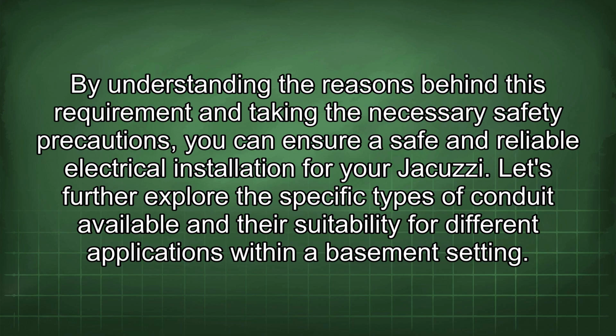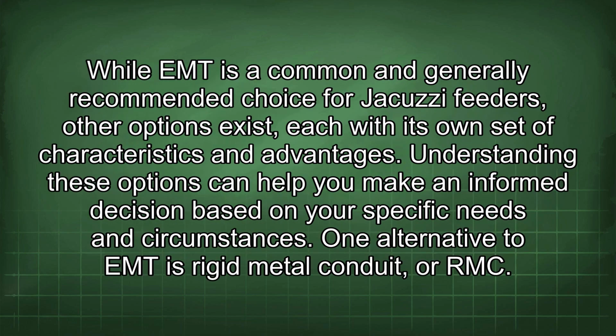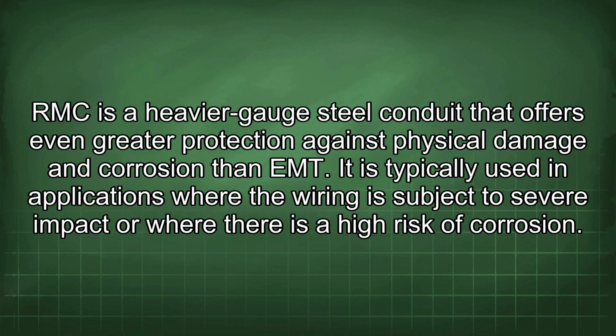Let's further explore the specific types of conduit available and their suitability for different applications within a basement setting. While EMT is a common and generally recommended choice for jacuzzi feeders, other options exist, each with its own set of characteristics and advantages. Understanding these options can help you make an informed decision based on your specific needs and circumstances. One alternative to EMT is rigid metal conduit, or RMC. RMC is a heavier gauge steel conduit that offers even greater protection against physical damage and corrosion than EMT. It is typically used in applications where the wiring is subject to severe impact or where there is a high risk of corrosion.